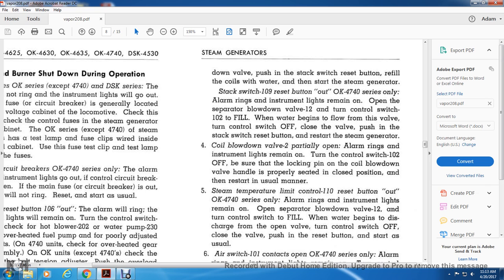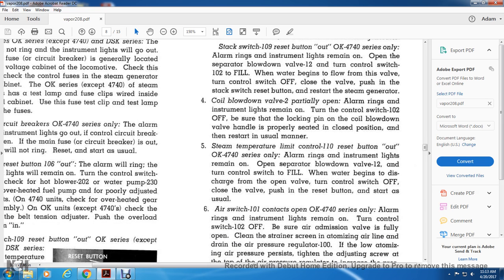4. Coil blowdown valve 2 partially open only. Alarm rings, instrument light remains on. Turn the control switch 102 off. Be sure the locking pin of the coil blowdown valve handle is properly seated in the closed position and restart in the usual manner. 5. Steam temperature limit control 110 reset button out, OK 4740 series only. Alarm rings, instrument lights remain on. Open separator blowdown valve 12 and turn control switch to fill. When the water begins to discharge with the valve open, turn the control switch off.